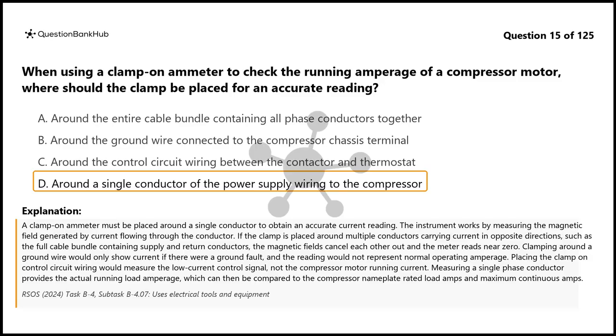Clamping around a ground wire would only show current if there were a ground fault, and the reading would not represent normal operating amperage. Placing the clamp on control circuit wiring would measure the low current control signal, not the compressor motor running current. Measuring a single-phase conductor provides the actual running load amperage, which can then be compared to the compressor nameplate rated load amps and maximum continuous amps.